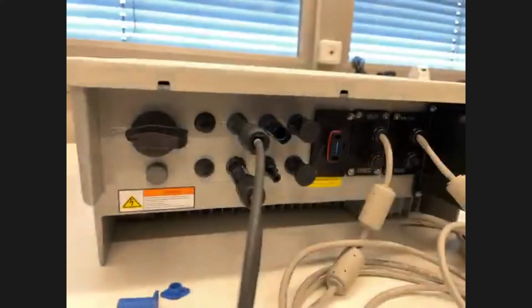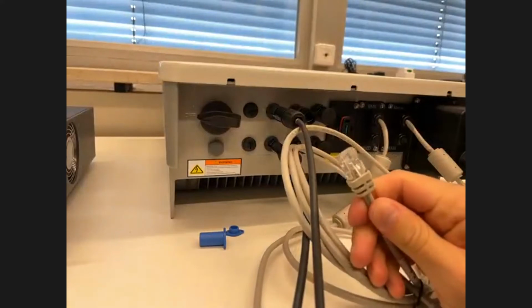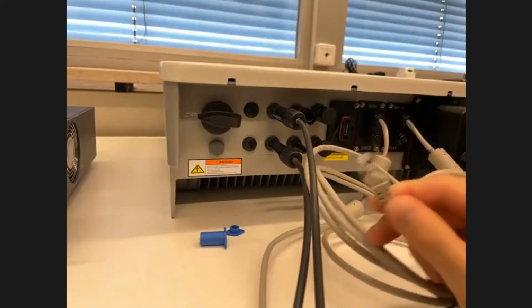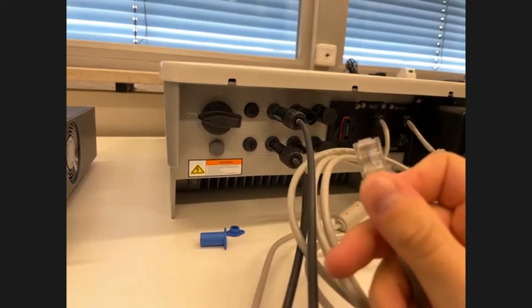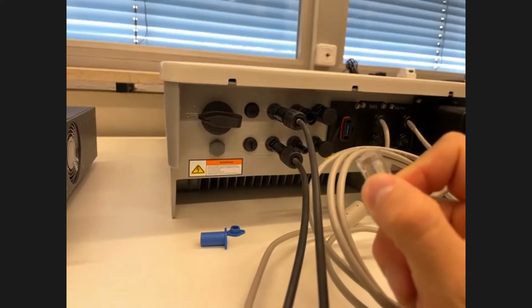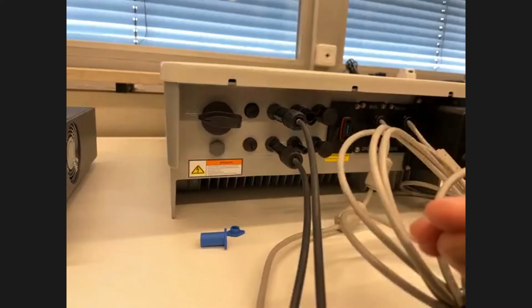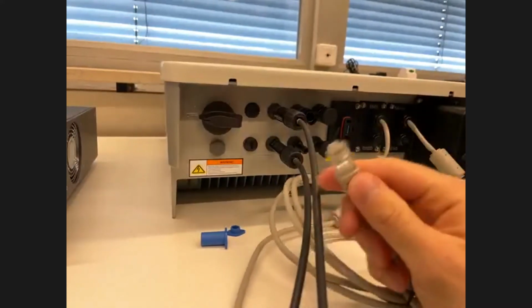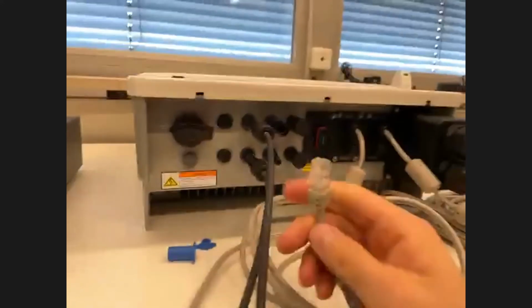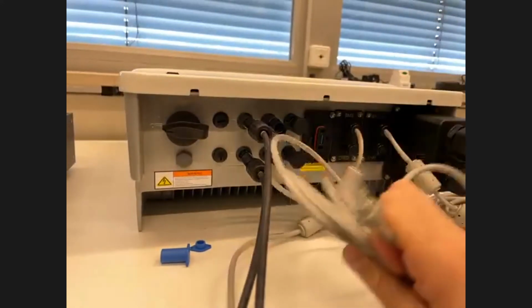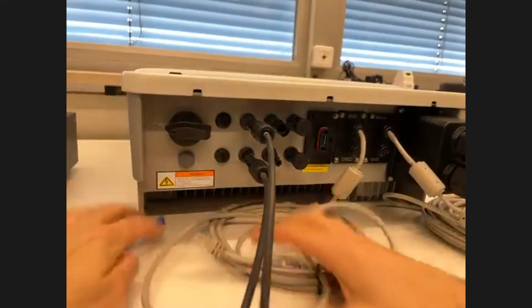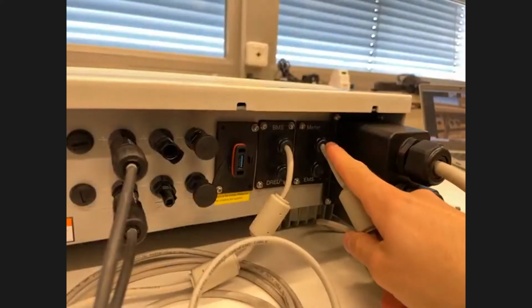Okay, so attached again. Here is the battery communication cable. As you see here, this is a normal RJ45 cable, and you can even see that only two pins of this are connected, so you can see which pins are connected. You can also read in the manual which pins of this one are used. You can either connect this directly to the battery, or you just cut the cable and use the cables inside. Here on the left side is the connection to the meter.